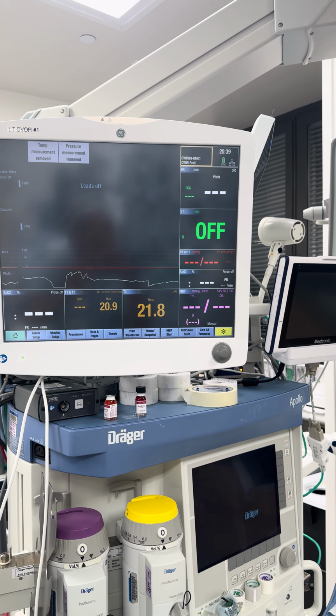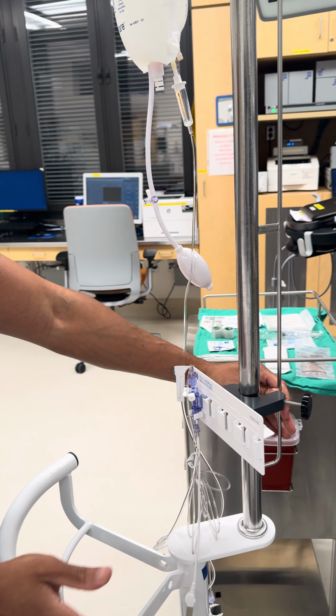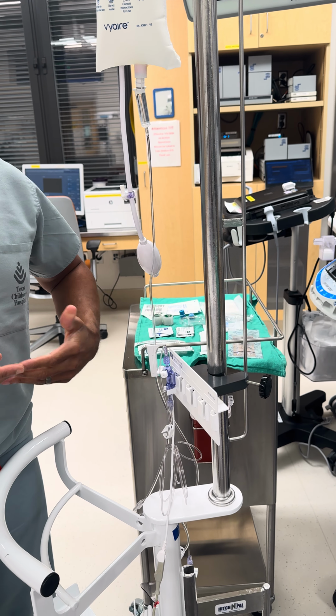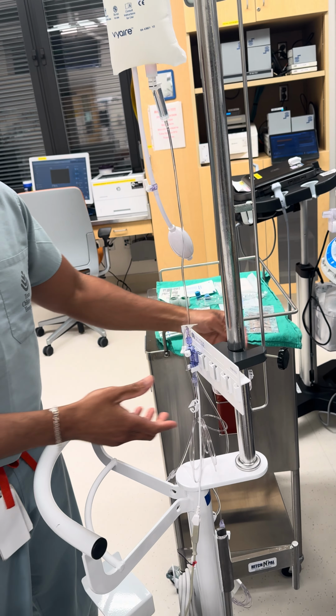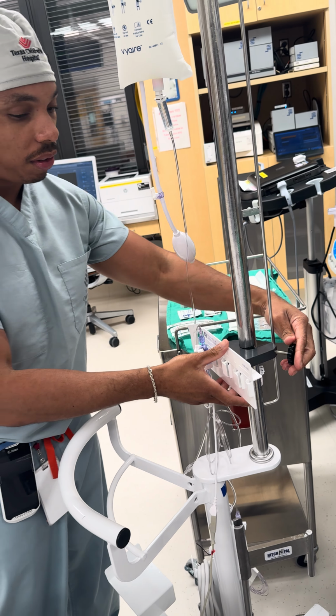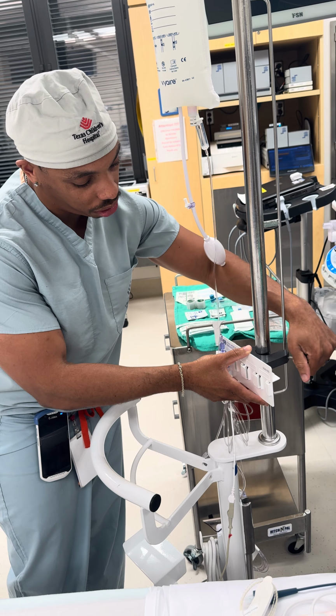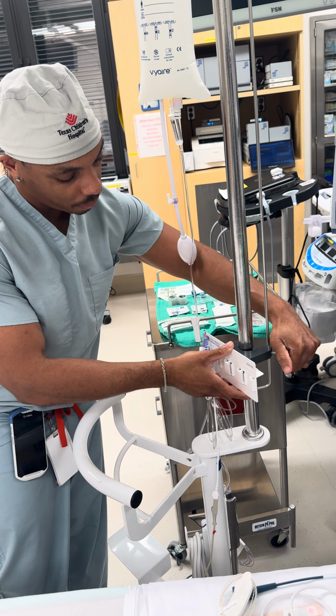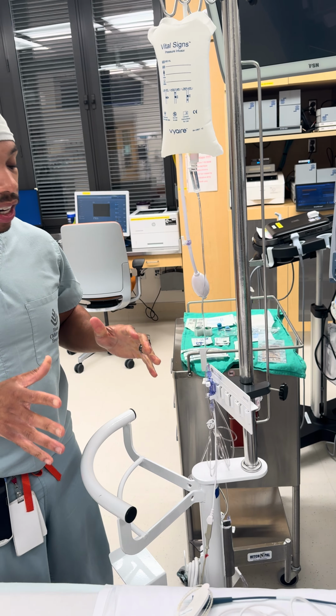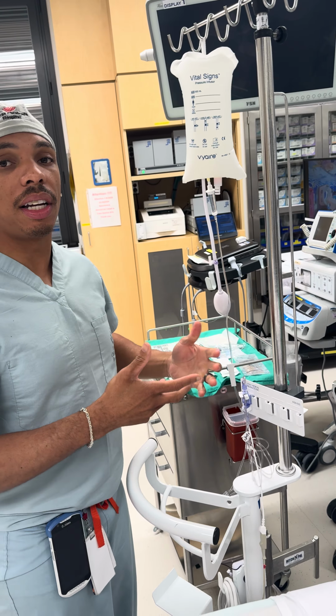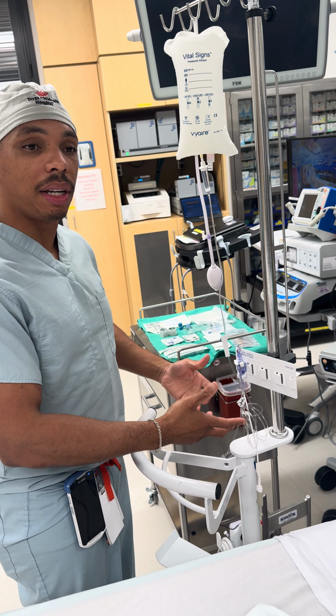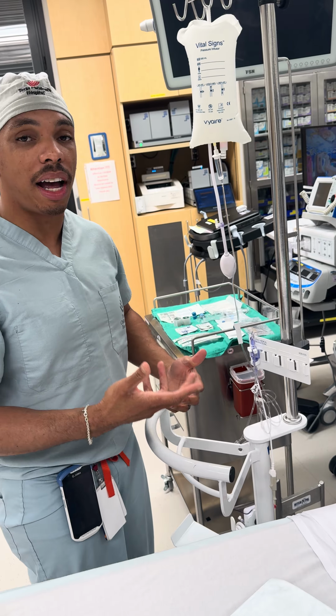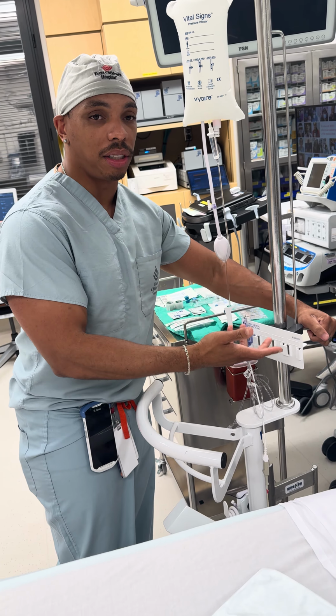So the first thing we're going to do is make sure that this plate is at the phlebostatic axis of the patient. And what that just means is it's mid-level at the patient's chest. So you wanna make sure that's right midline with that patient's chest, which should be around right here. And like I say, it's important to zero at the phlebostatic axis, because if you zero it too high, your baseline is going to be wrong. And if you do it too low, the same thing. It's not going to be calibrated at the right height. So you have to do it exactly at that patient's mid-level.